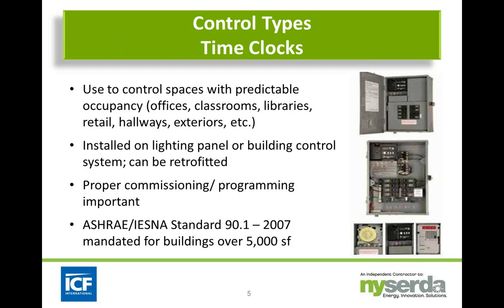A key item with installing time clocks is proper commissioning and programming. If the time settings aren't set correctly, it can throw off the whole process, and people will try to disable the time clocks. One good solution is an astronomical time clock, which lets you plug in the location of the building so it can adjust based on changes in sunrise and sunset throughout the year.